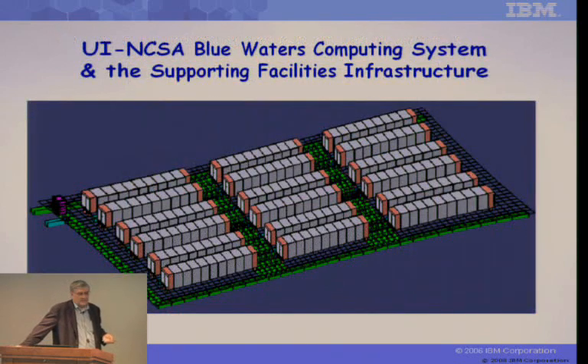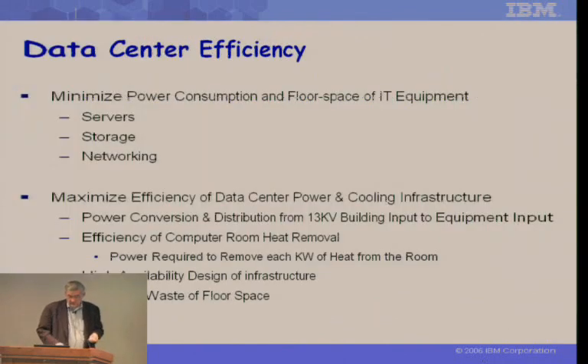This is a layout, about what's shown here, about 150 racks, something like that. So we did really carefully look at the whole design here, all the way from the ambient all the way into the processors when we put this together. So the idea was, how can we make this the most energy efficient that we could? So we looked at server storage and networking, power conversion from the 13,000 volts that comes into the building. How do we distribute that to make it most efficient? Heat removal, basically we're taking all the heat load out at the rack. So we won't have really any need, there is some, but any need for computer room air conditioning units in the data center. High availability design for the infrastructure. We have multiple feeds from substations on the campus. And of course, we're packaging everything very tightly, so minimum waste of floor space.